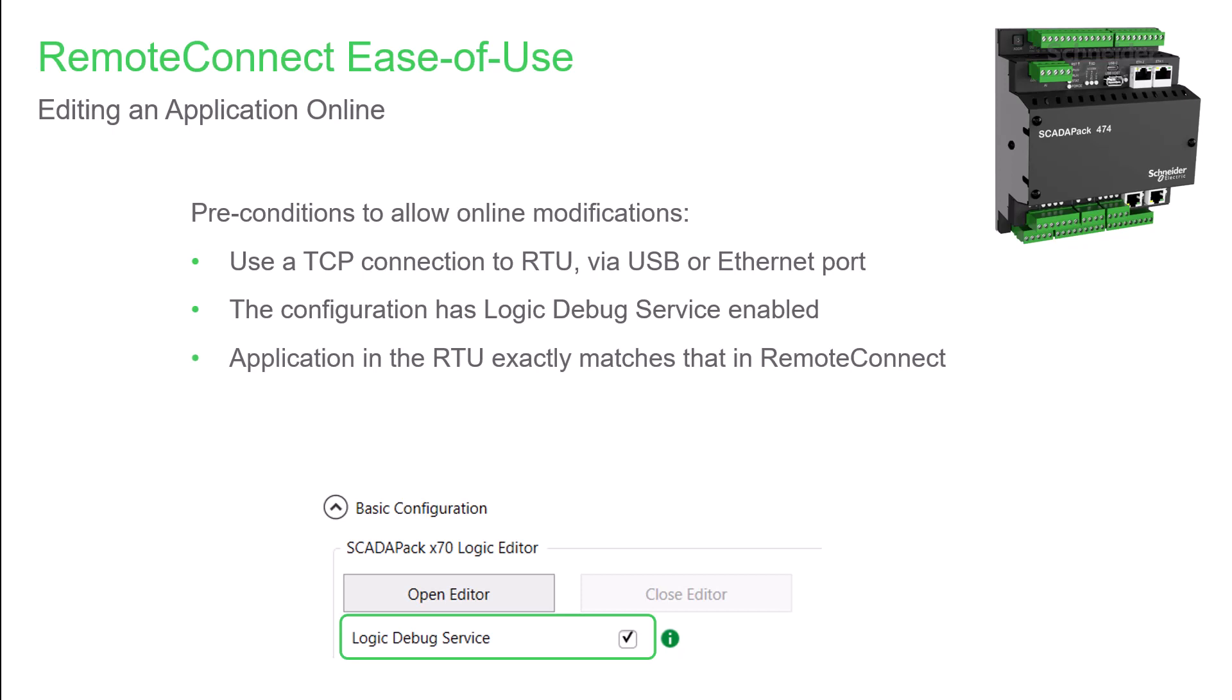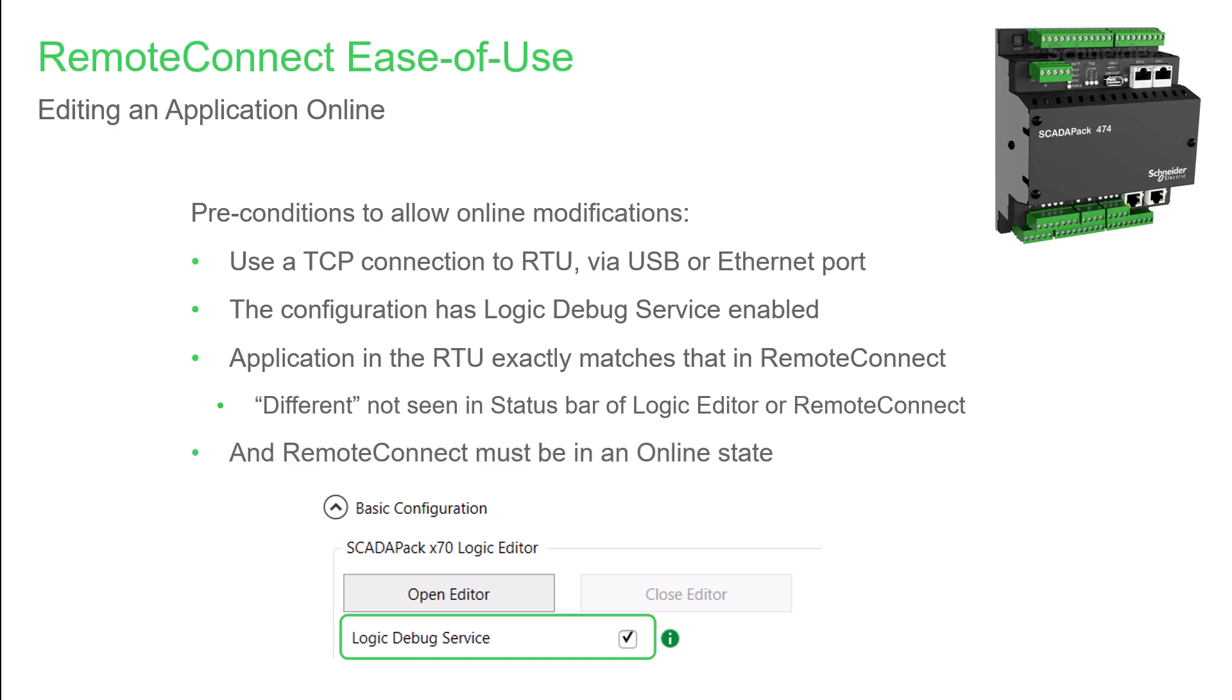The application in the RTU needs to be the same as in the RemoteConnect software. This can be verified by checking that 'different' isn't displayed in the status bar of either RemoteConnect or the Logic Editor. And not surprisingly, you do need to be online with the RTU.